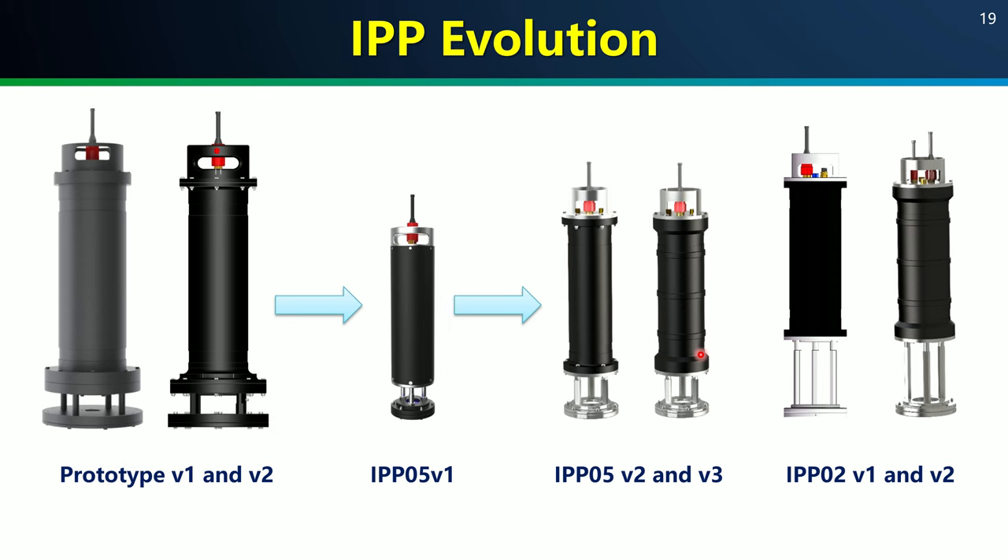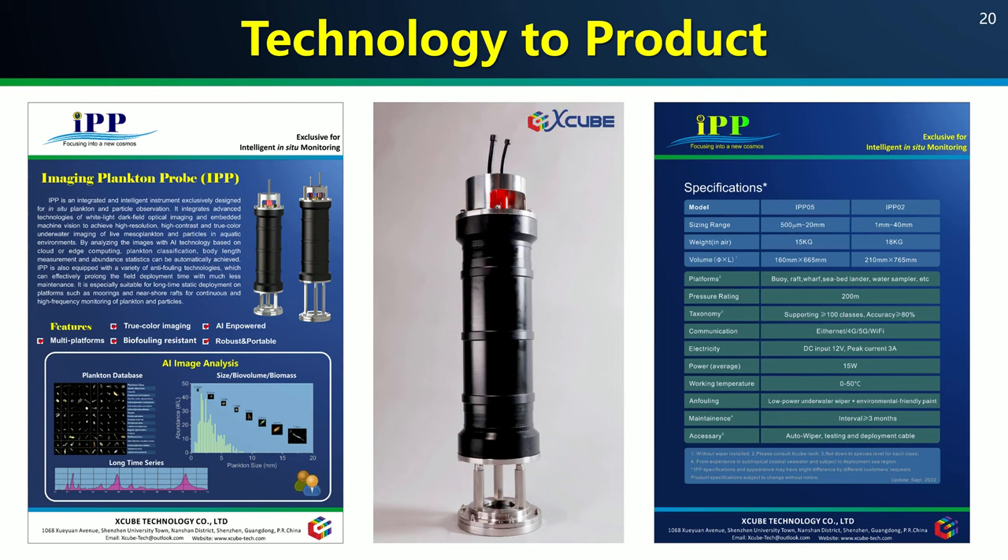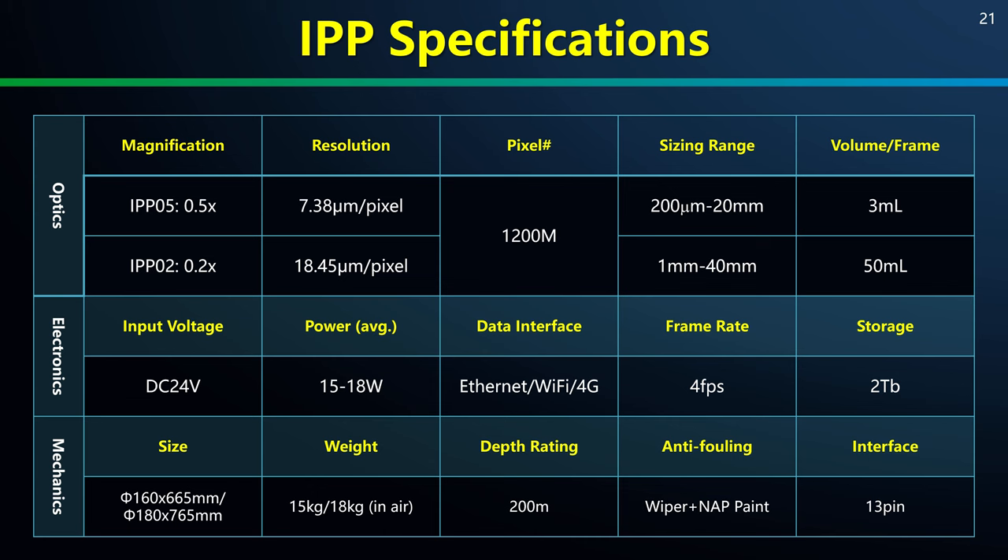Like many other known in-situ instruments, IPP has evolved from its prototype to new versions since its birth about six years ago. It is now smaller, lighter, and more mature. We spun off a company called Xcube dedicated to making it from a usable research tool into a useful instrument product for more users. The latest version has two magnifications supporting two sizing ranges, with an average power consumption of just 15 to 18 Watts, making it compatible with many platforms besides the buoy.